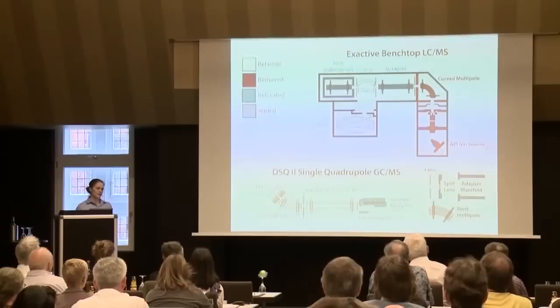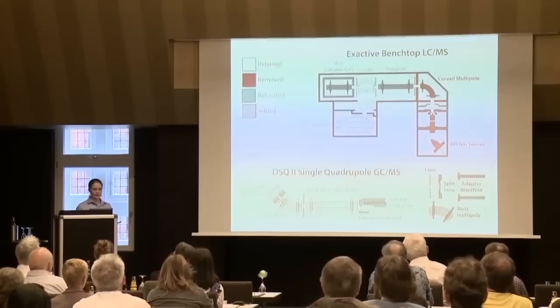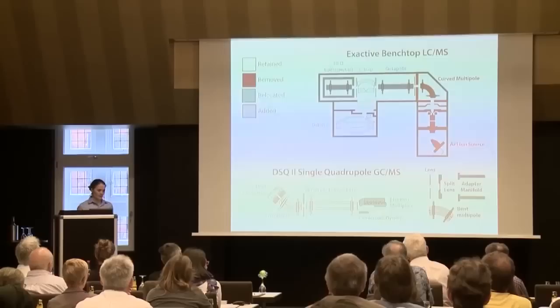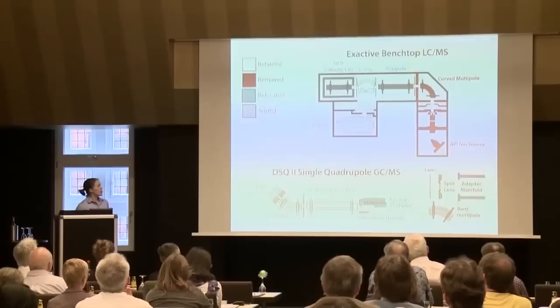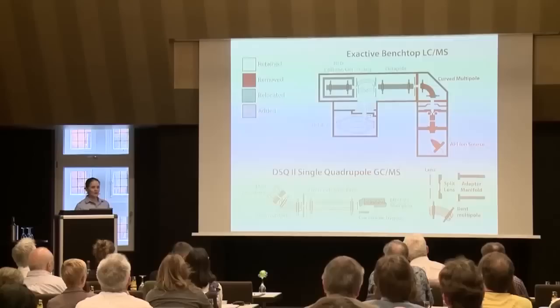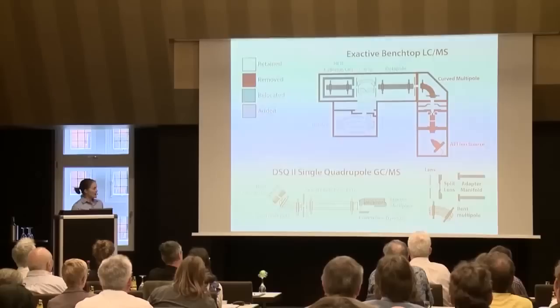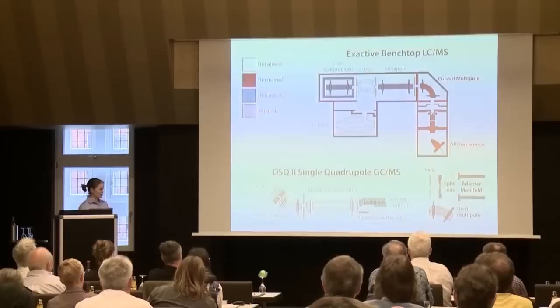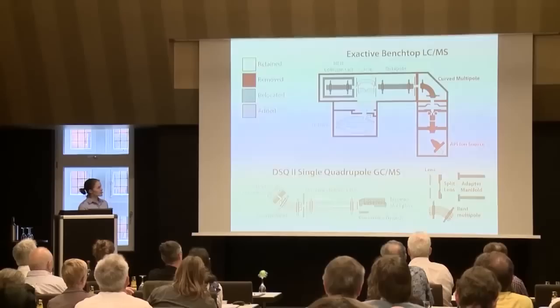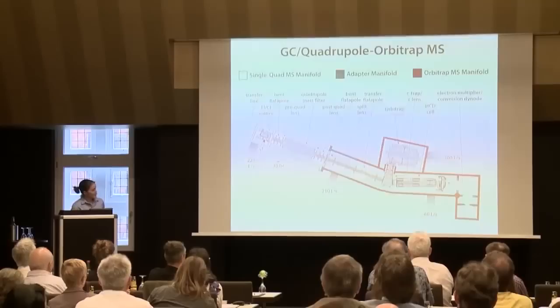After showing as a proof of principle on a LTQ orbitrap enabled with ETD that GC-created, or electron ionization-created ions could be analyzed in an orbitrap, we went on to trying to build something that would be useful to the community, with potential for commercialization. That was based on the Exactive benchtop LC-MS, which has an atmospheric ion source. Ions are directed then into the C-trap and the orbitrap. To provide our interface to the gas chromatograph, we took a single-quad GC-MS, and by removing and plugging this area, flipping these around, we were able to plug in the GC on this side to form this monster.